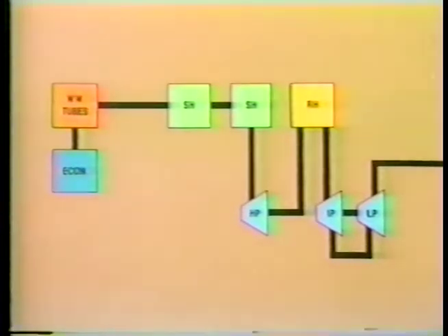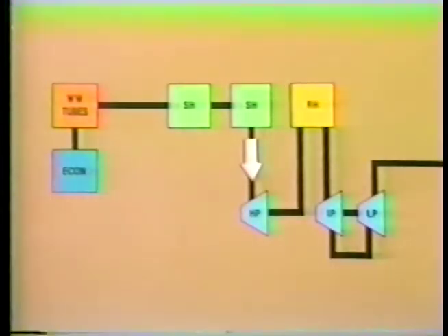We'll use this block diagram of the flow path of water and steam through a once-through boiler to explain the different modes. During the normal operation of a once-through boiler, any given quantity of water is transformed into steam in one pass through the steam-water circuit. The water is first supplied to the economizer, then the water wall tubes. In the water wall tubes, the water is subjected to pressures and temperatures above the critical point, causing it to transform into steam. The steam continues from the water wall tubes through the primary and secondary superheaters, the high pressure section of the turbine, back to the reheat section of the boiler, and on through the intermediate and low pressure sections of the turbine.